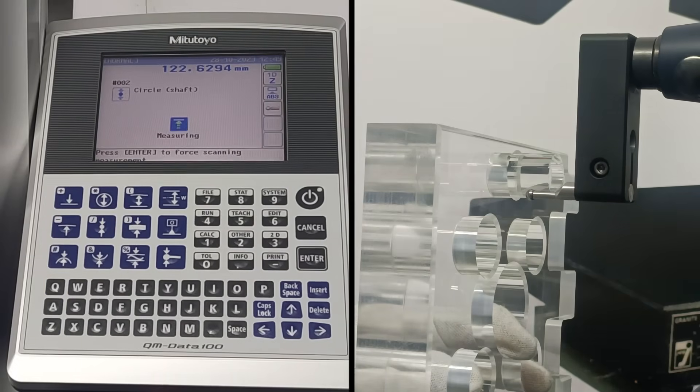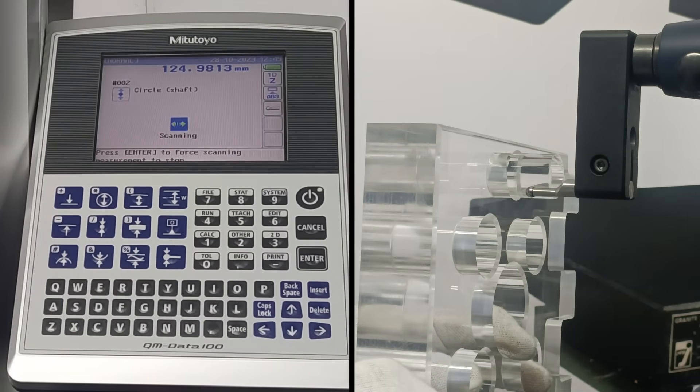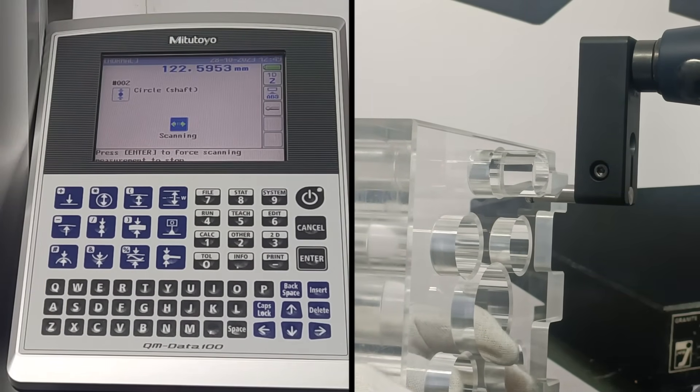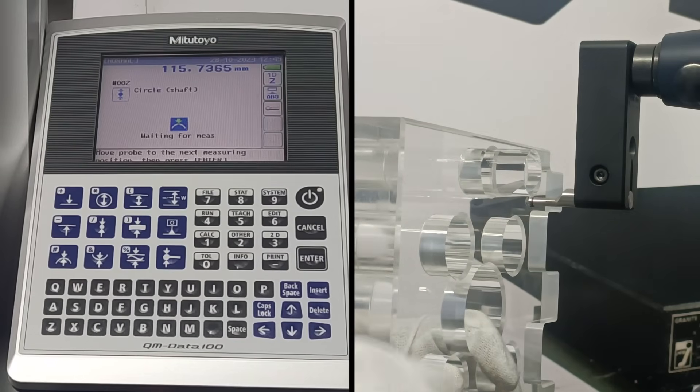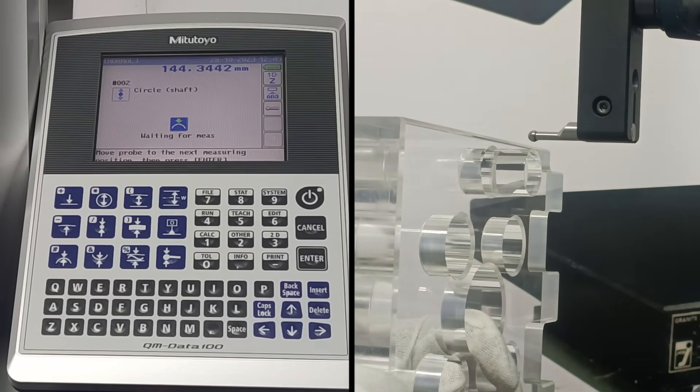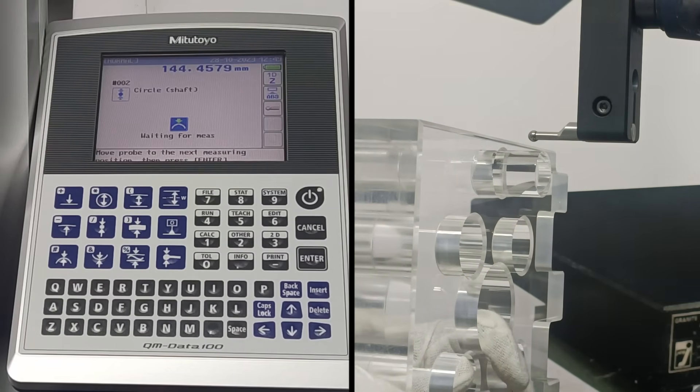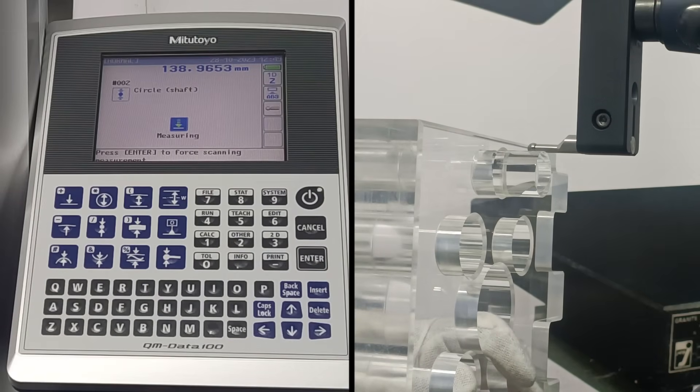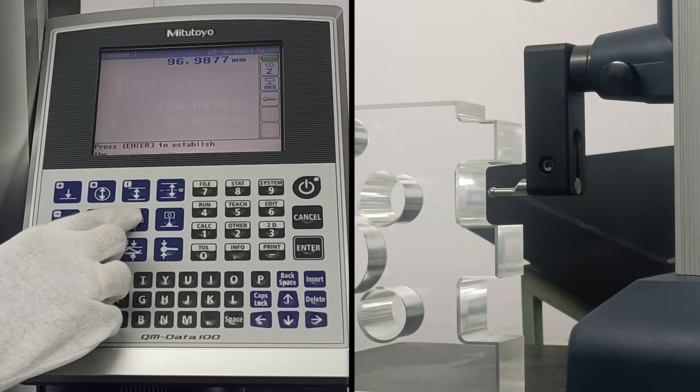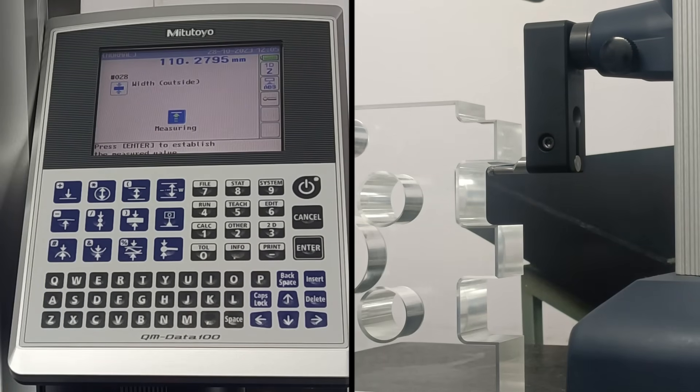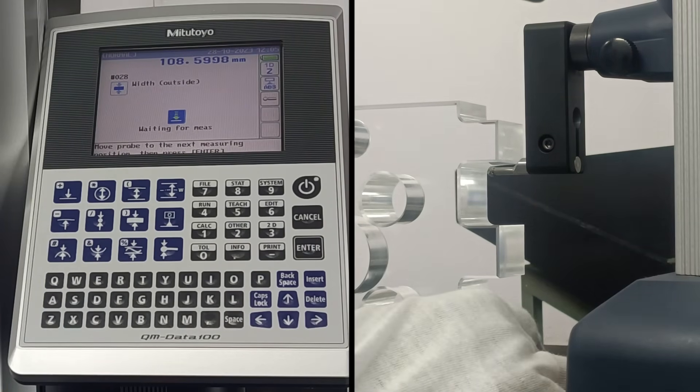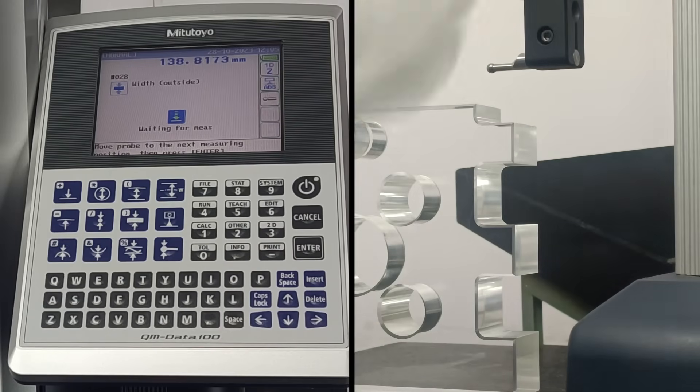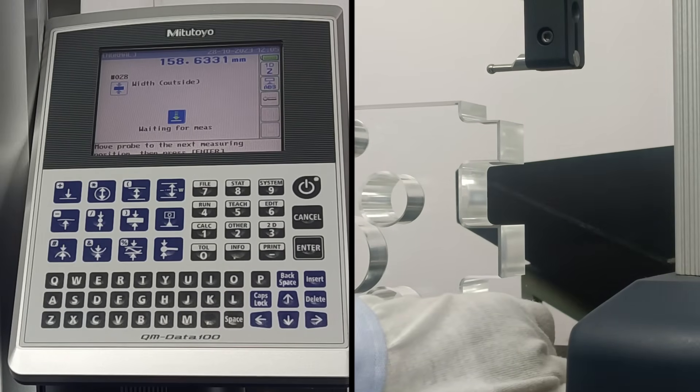This function performs scanning measurement on the bottom and top of a shaft. Move the probe to the bottom contact surface and scan. Then move the probe to the top contact surface and scan to determine the shaft's diameter and center coordinate axis. This function measures the bottom and the top position of an outside width element to determine the outside width W and the center coordinate axis Z.